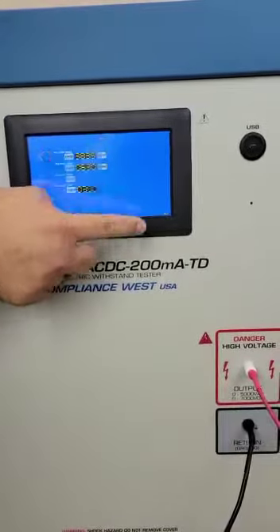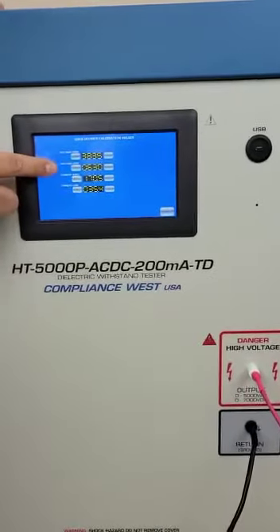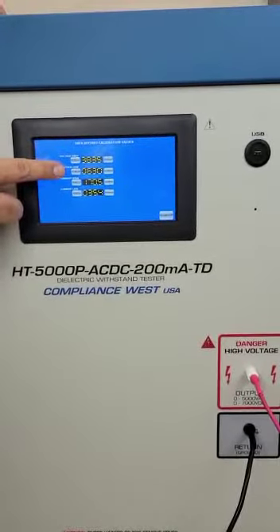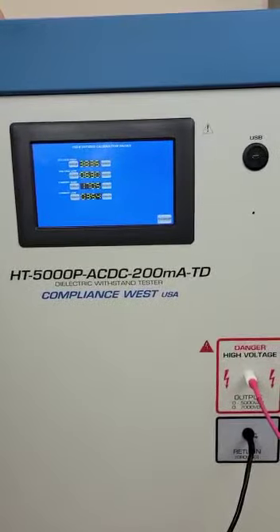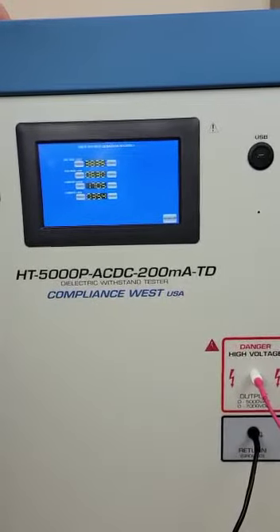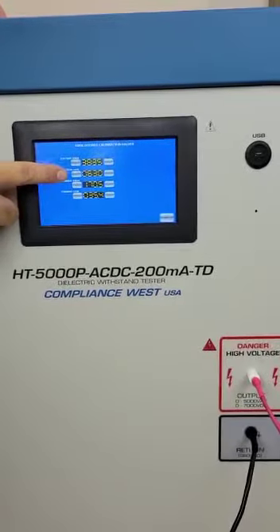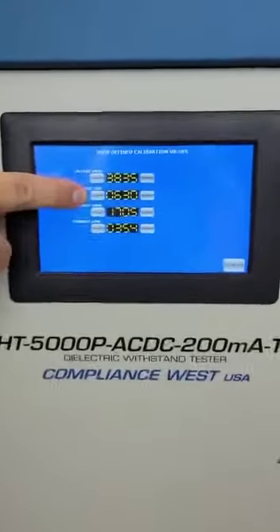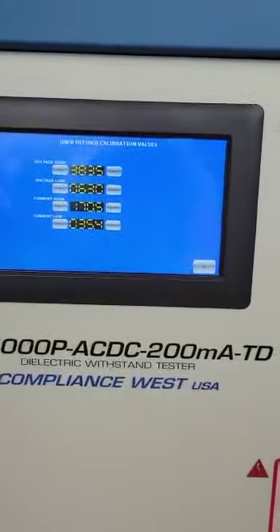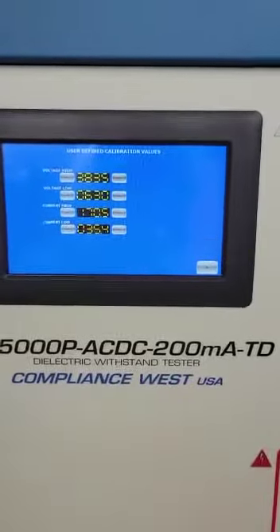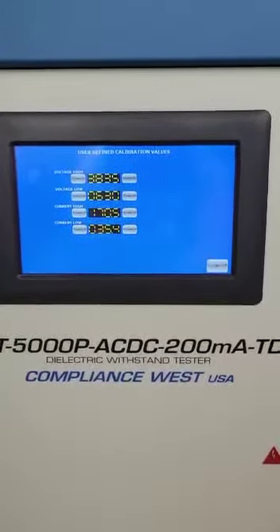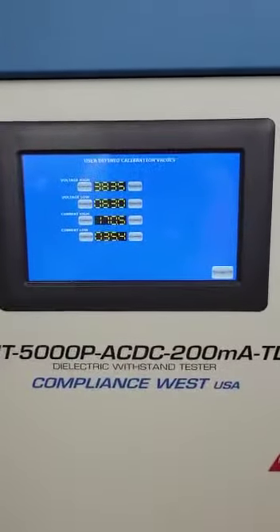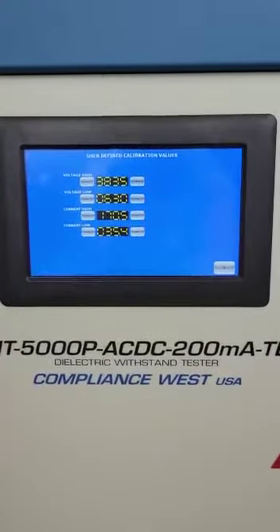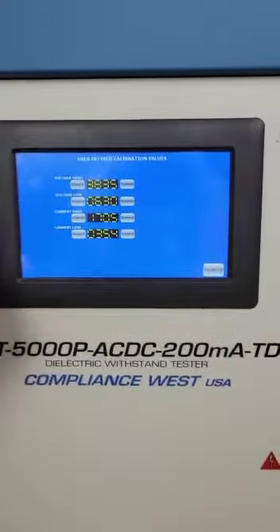You're gonna release the test. You're gonna go back to the screen, and you are going to enter the multimeter voltage in the voltage low, which is the second line. In this case, we are seeing our calibration. This is how it was saved when we performed calibrations. We had a value of 630.